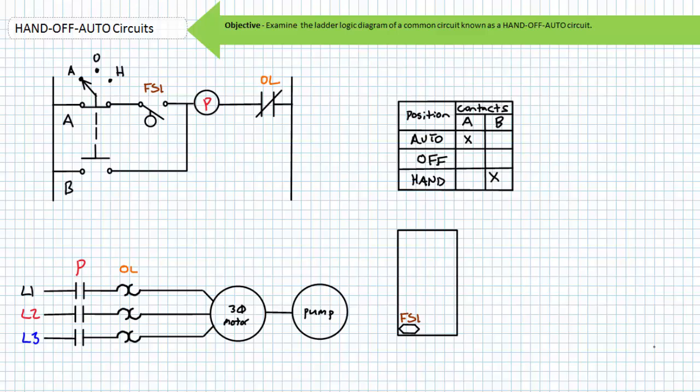When the selector switch is in the auto position, the pump motor will run when the float switch closes. The overloads serve to protect the pump motor from sustained overload conditions.